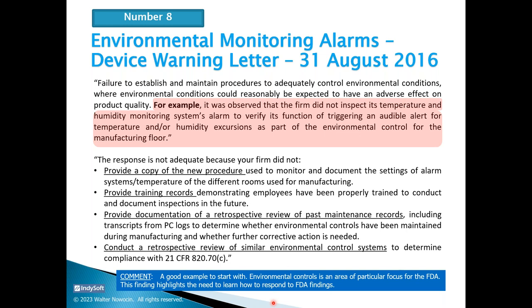We'll start with a good example: environmental monitoring alarms, one of the FDA's focus areas. The finding states that the firm did not inspect its temperature and humidity monitoring system alarm to verify its function of triggering an audible alert upon temperature and humidity excursions, as part of the environmental controls for the manufacturing floor. Now let's look at the response.